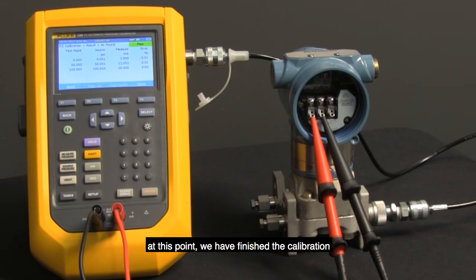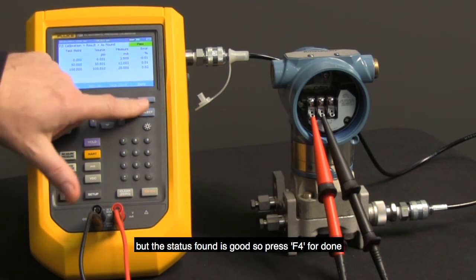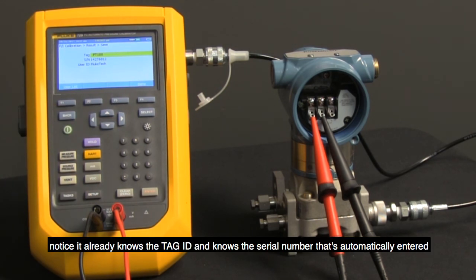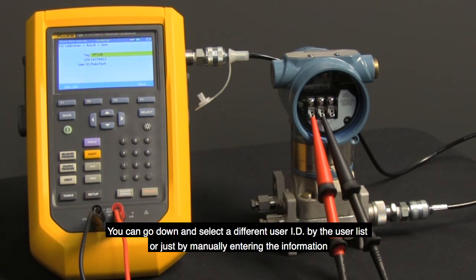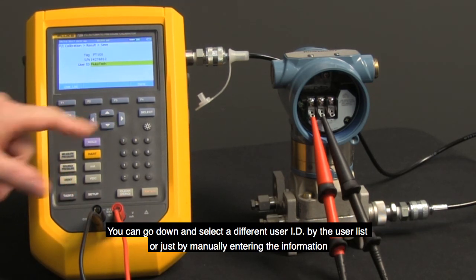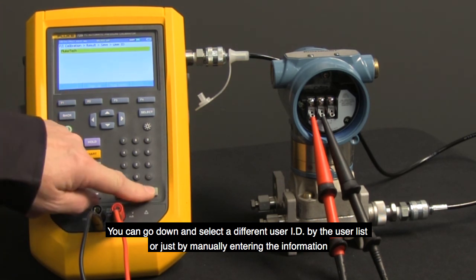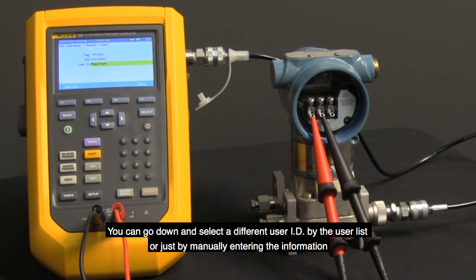At this point, we have finished the calibration. If it was out of spec, we'd have to make adjustments and then do an as left, but the status found is good. So press F4 for done. Notice it already knows the tag ID and serial number that's automatically entered. You can go down and select a different user ID by the user list or just by manually entering the information.